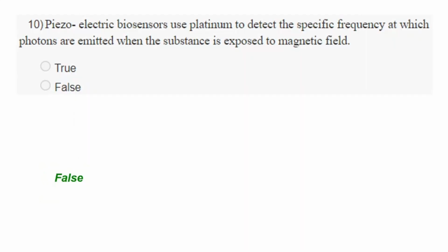So the statement that is written here is not entirely accurate. Piezoelectric biosensors do not typically use platinum to detect the specific frequency at which photons are emitted when the substance is exposed to a magnetic field. Piezoelectric biosensors rely on the piezoelectric effect, which is the ability of certain materials such as quartz or ceramics to generate an electrical charge in response to mechanical stress. When a piezoelectric material is mechanically stressed, it produces a voltage difference across its surface, which can be measured and correlated to the amount of stress applied.